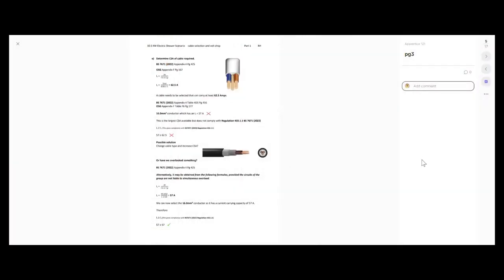So far we've worked out our design current and the rating of our protective device. The next thing is to calculate how much current the cable I'm going to select needs to carry, based on grouping with the other circuit. To calculate IZ, we divide the rating of our protective device by any correction factors. So it would be 50 amps divided by 0.8 — our correction factor for grouping — which comes to 62.5 amps. We've gone from 45 amps design current, but because the cable is grouped, it now needs to be able to carry 62.5 amps.